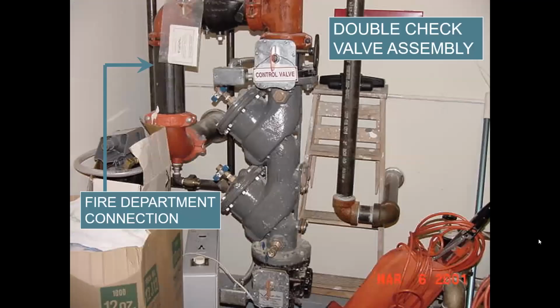So in this case, we have a double check valve that is being used with the fire system. Again, we can look at that real quick. There's no relief port with it. This, again, is an acceptable setup to protect a fire suppression system if the local fire department does not use additives and they only use potable water when filling their trucks. If any of that changes, or if any of that is in doubt, there should be an RPZ put in place.